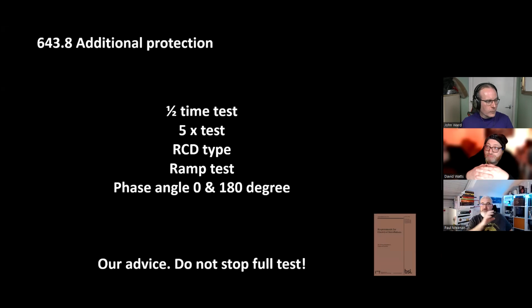That has disappeared now to just test at the RCD, which is wrong. Because if I test at the end of the line of a radial, let's say in my living room downstairs, and I have a capacitive effect because of printed circuit boards in parallel and various other bits, then should I even be selecting an RCD? Or can I actually rely on the RCD's performance? Probably not. And we will go into that in more detail on our RCD webinar, which I've been writing for 4 years now. It's nearly ready. But we now need to tie in this, and worst case scenario, always.